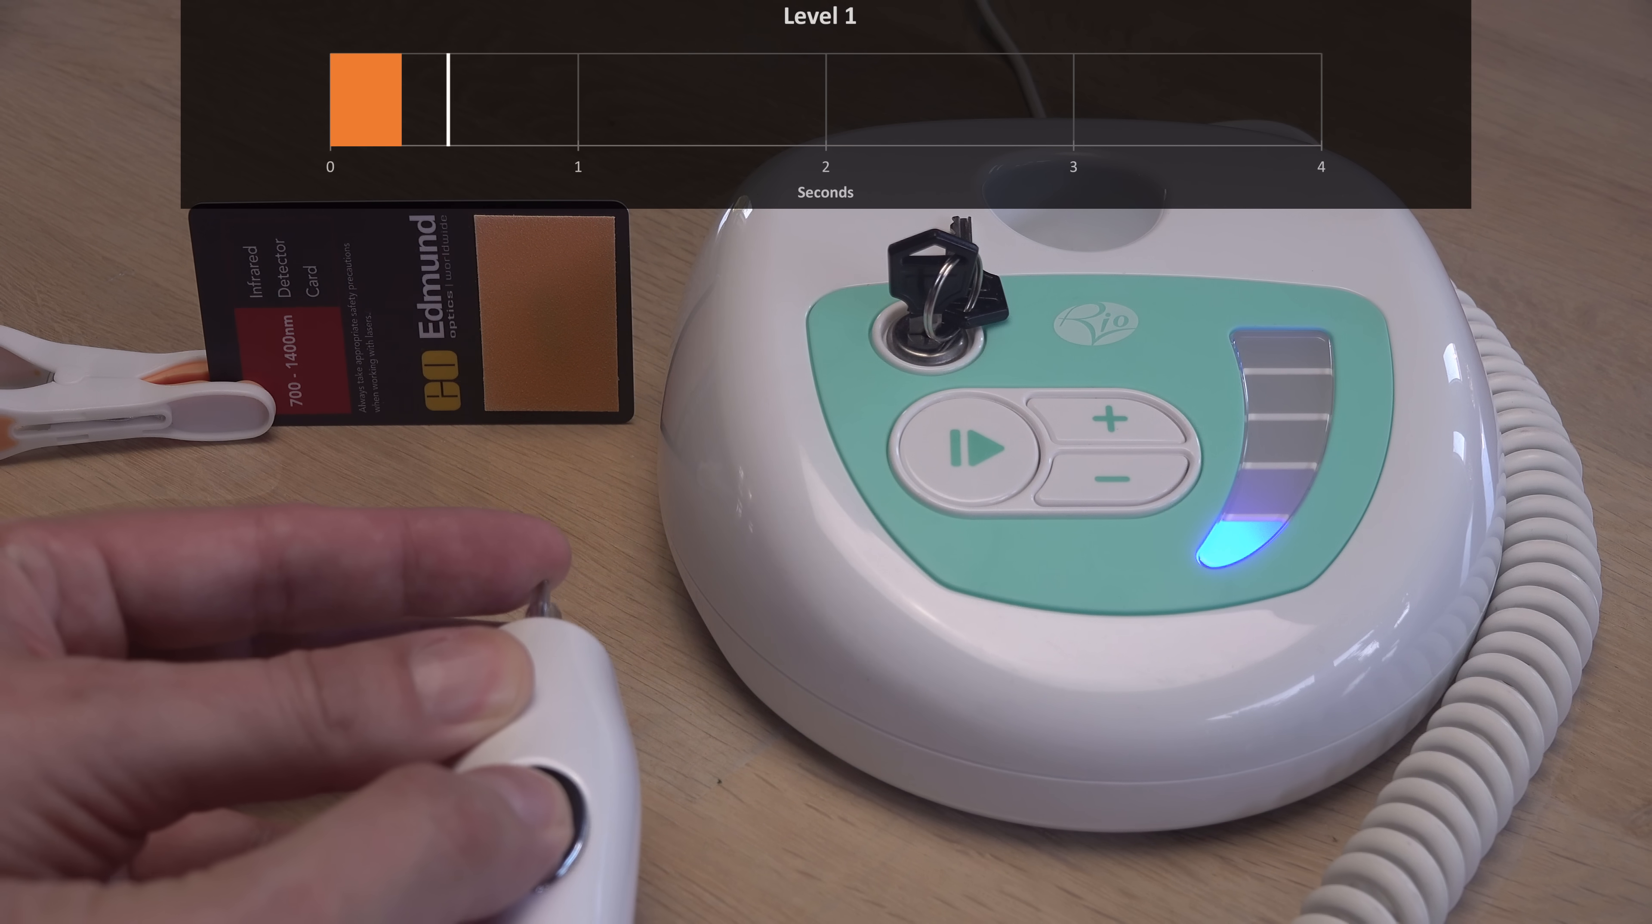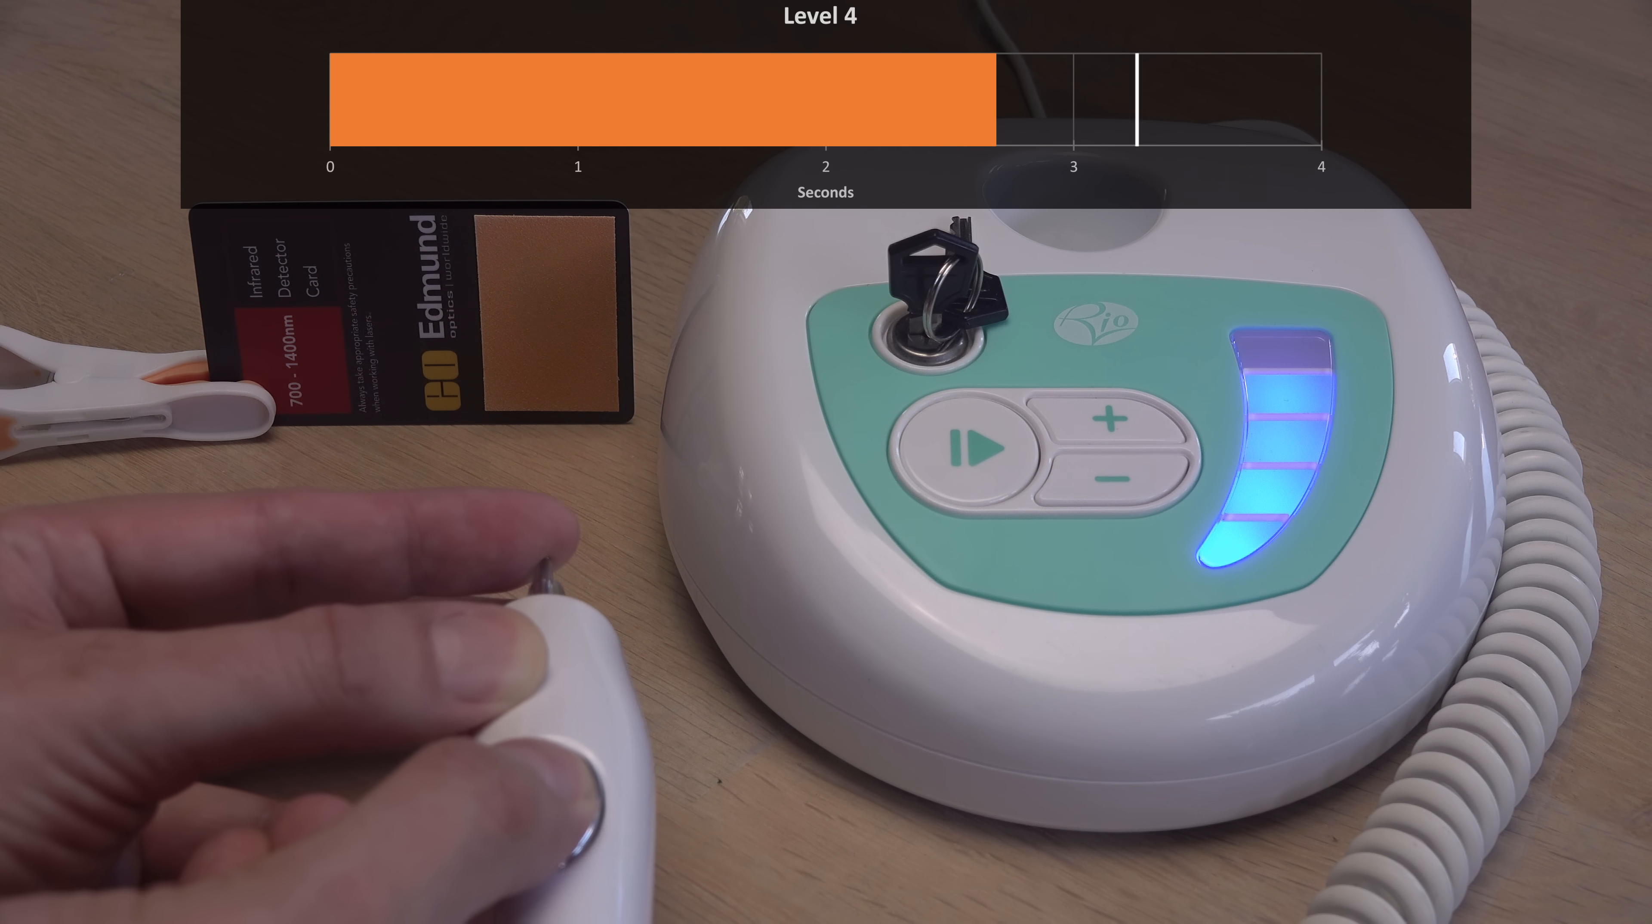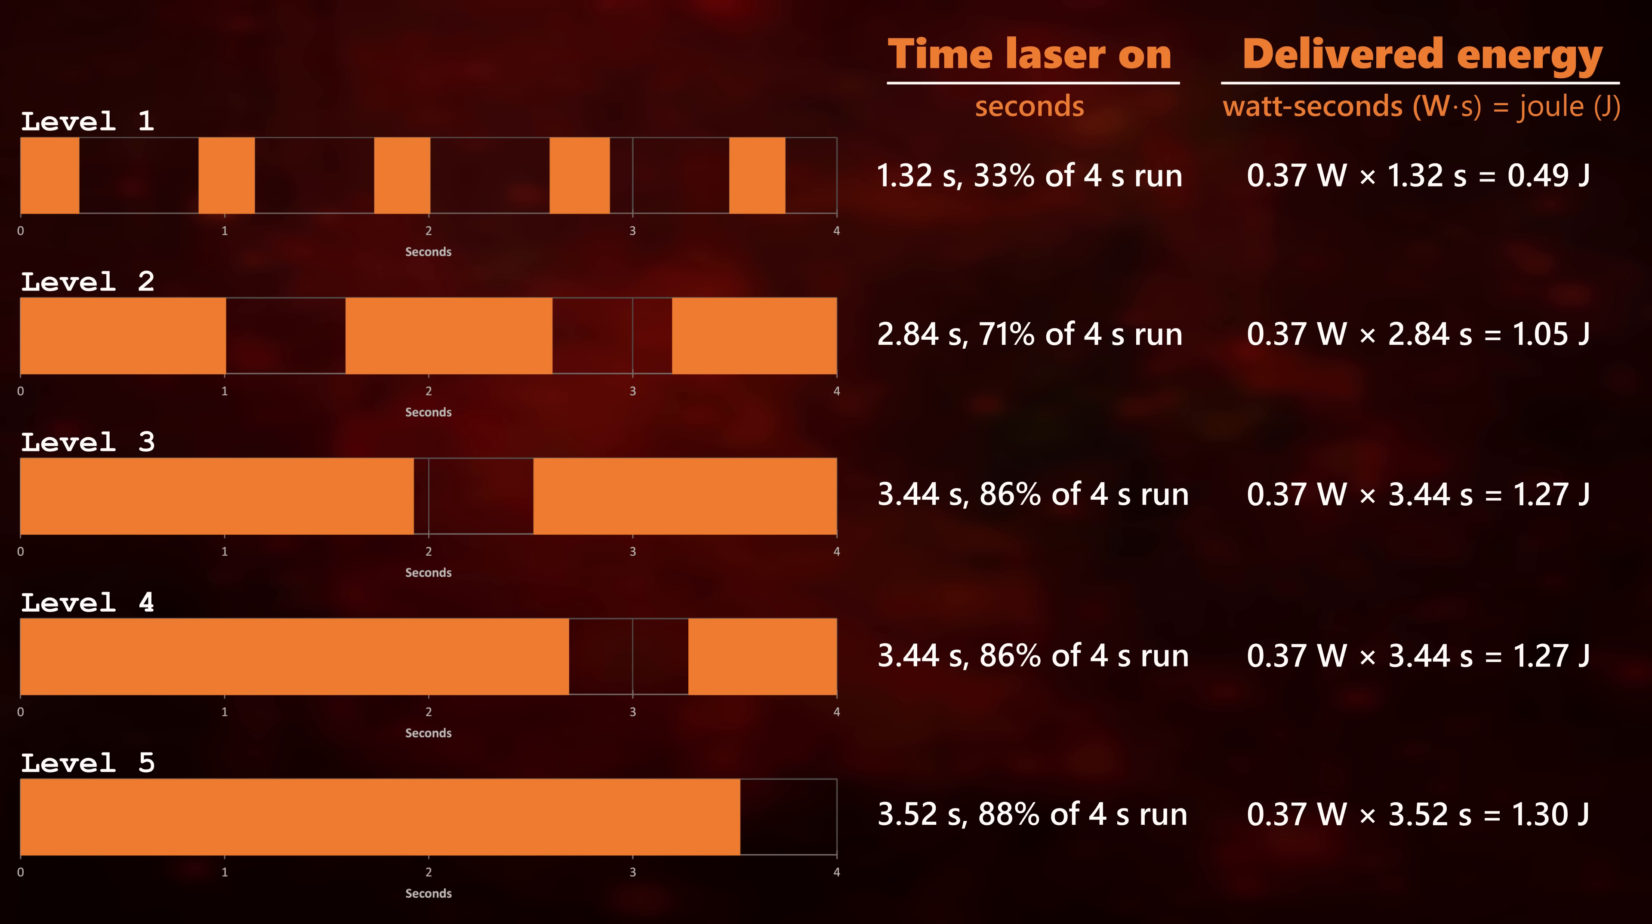I have mapped the different energy settings using an infrared detector card. Notice how similar the total energies are between the stronger settings but the heating effect is not because the lower settings have a shorter main pulse giving a lower peak temperature.